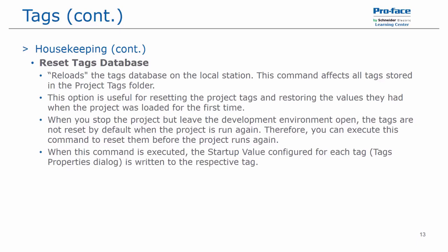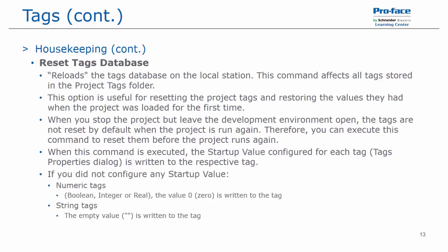And when I say reinitialize or reload, that doesn't necessarily mean resetting them to 0. There is a startup value that you can configure for the tag. And this startup value is what the tag is reinitialized to. However, if you do not configure a startup value for a tag, they will be set to the defaults. For numeric tags, those are booleans, integers, or reals, it's a value of 0. For string tags, it is an empty string.